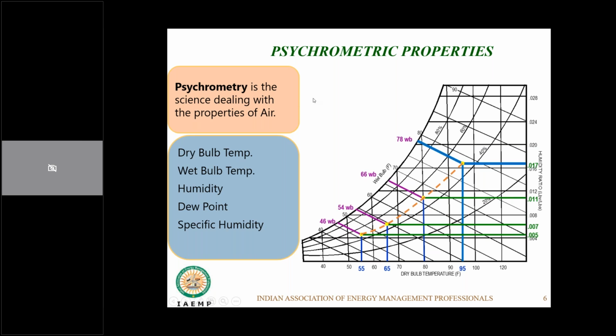Now what happens? Let's say we again reheat this air from 50 degrees Fahrenheit to my 80 degrees Fahrenheit. So when it comes back to 80 degrees Fahrenheit, now the relative humidity has come down from its original value of say 50% to a value of around 37-38%, which is below the 40% RH. If you see the saturation curve here, we are somewhere here, it is around 37%, and the specific humidity has come down to 0.008.